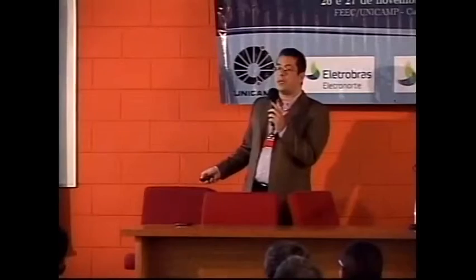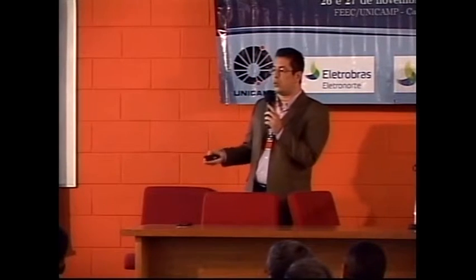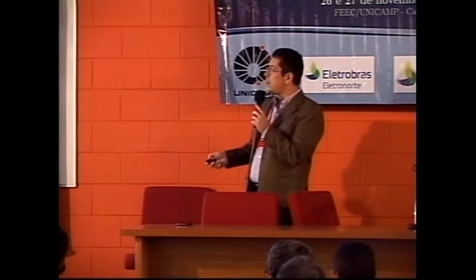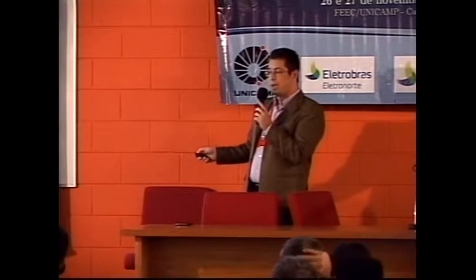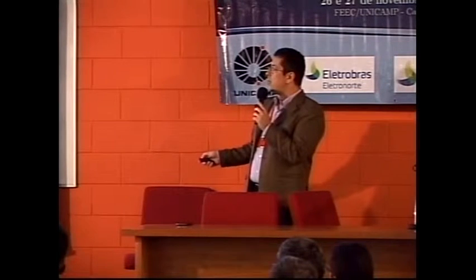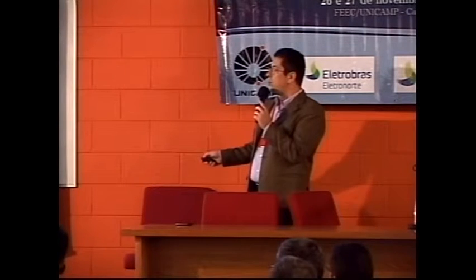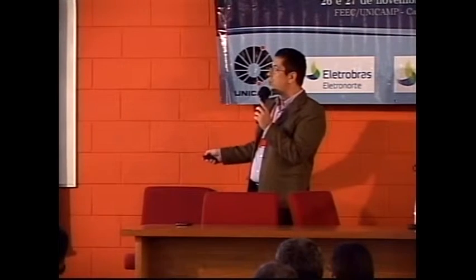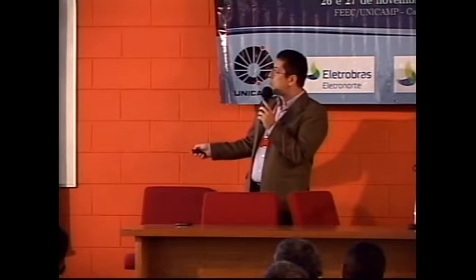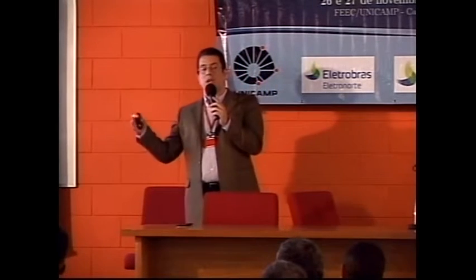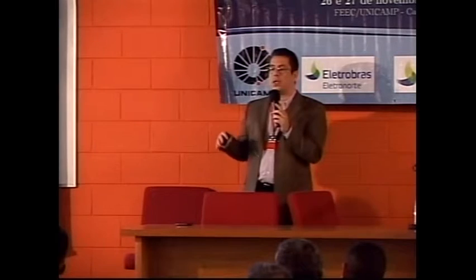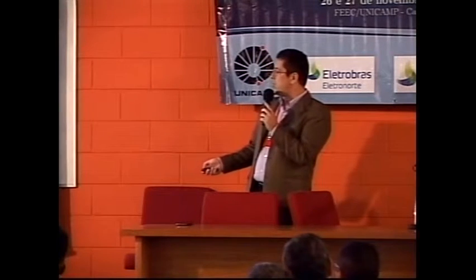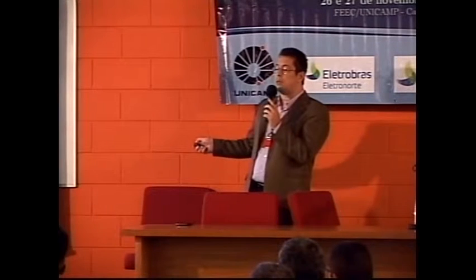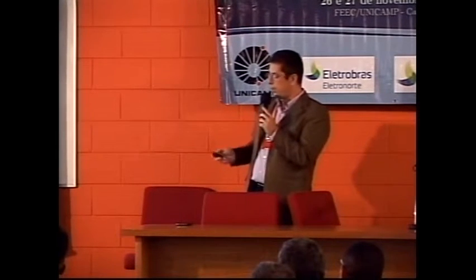There's always the issue of the increase of the characteristic power with price, because now I'm adding converters, so I'm going to raise the cost. These are expensive devices that require additional substations and controls. As an example, that line of 8.6 gigawatts and the event. So I initiate the tap and I drain energy from the tap as well as inject energy through the tap. And this is all a result. All these values were calculated coming from the circuit. This was all modeled on PSCAD, trying to reproduce the behavior of the circuit. And we notice that the load remains unaltered. The same thing for its reactive power.